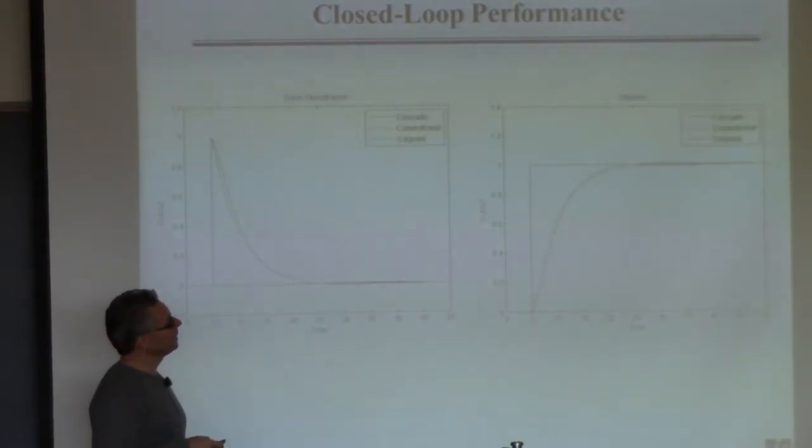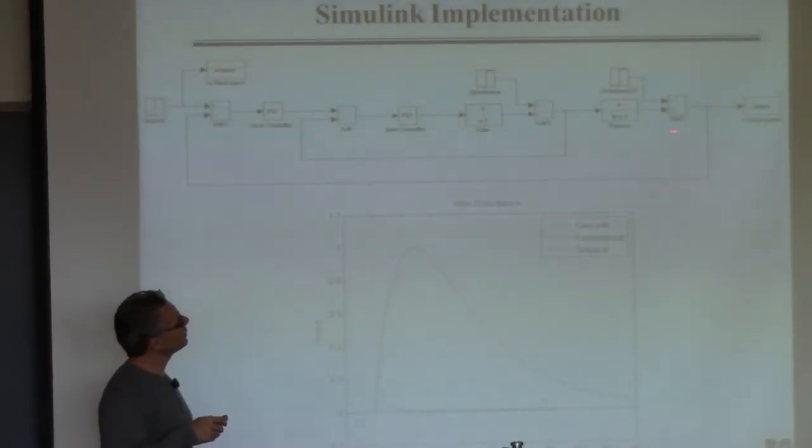So it's just critical to understand that this whole idea of cascade control is meant to reject disturbances you cannot measure that come into this inner loop. It doesn't help with anything else.